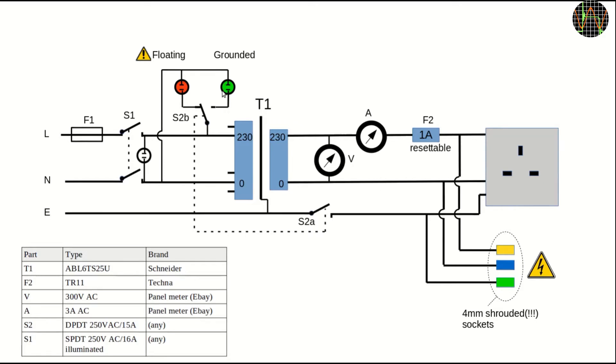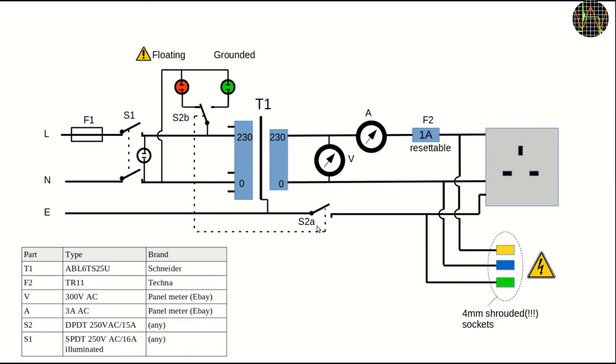As it is drawn, S2 is in a floating position and the red indicator would be lit. It goes without saying that you should occasionally check that S2 is still working correctly, rather than blindly relying on it. This can be easily done from the outside, testing the output earth for continuity against normal earth.